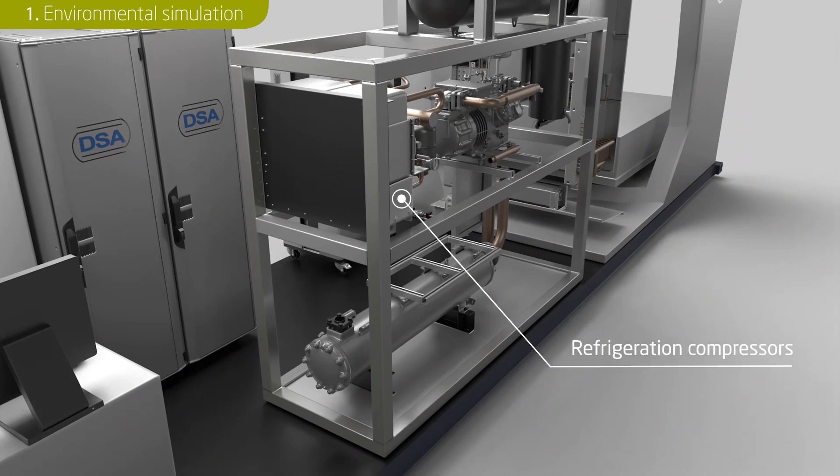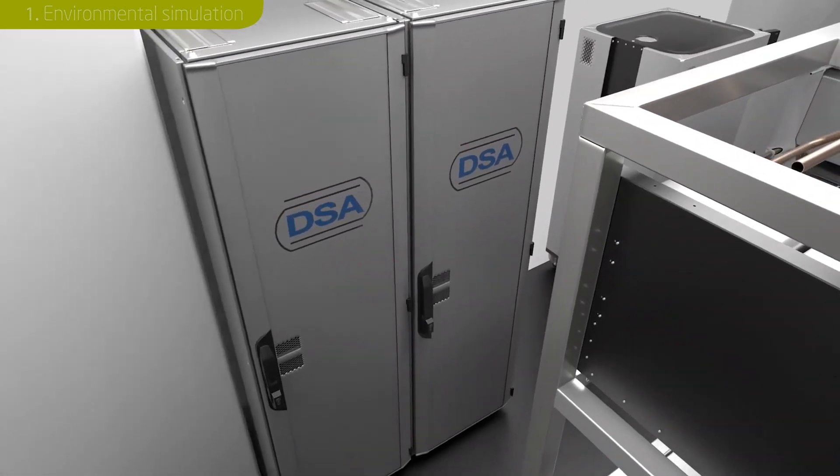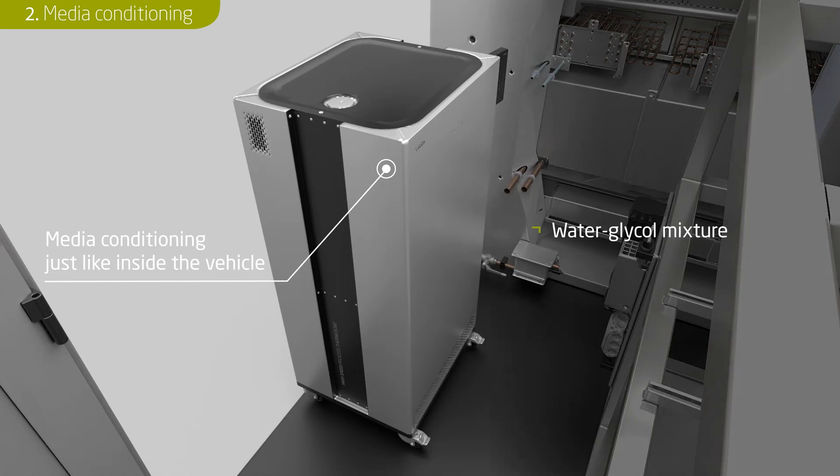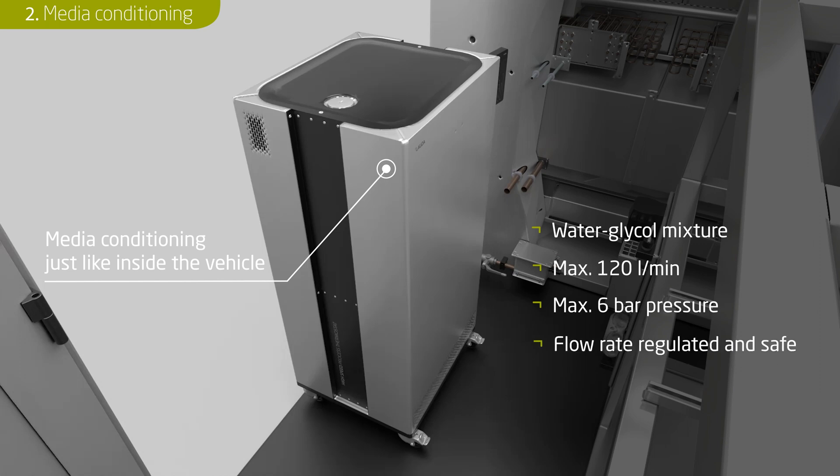The refrigeration compressors are compactly mounted on a frame in the container. The battery pack is connected to the media conditioning system just like inside a vehicle. Up to 120 liters per minute of water-glycol mixture is pumped into the battery pack at a maximum of 6 bar pressure to dynamically control the temperature of the test specimen. A flow control system with a magnetic inductive measuring method and adjustable pressure limiter is installed to protect the test specimen. The media conditioning can cool the test specimen down to minus 40 degrees centigrade or heat it with approximately 16 kilowatt.